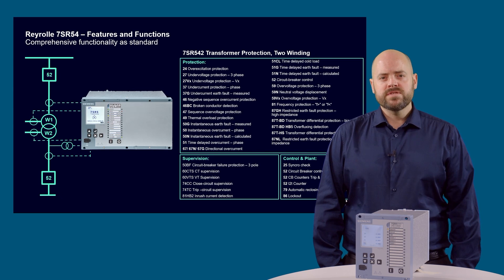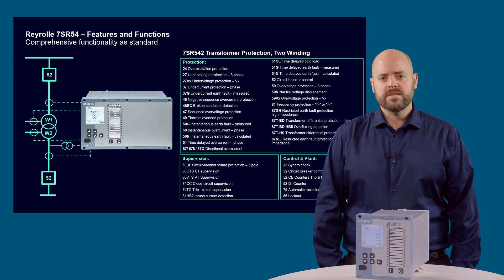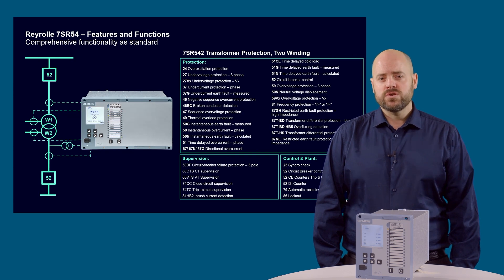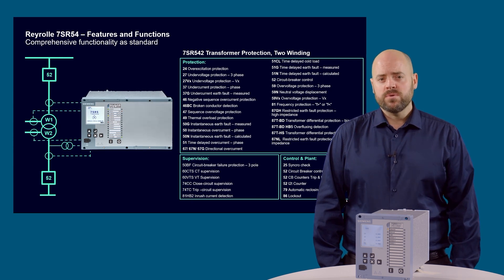The Reyrolle 7SR542 two-winding device provides comprehensive protection for two-winding transformers. The device also provides differential protection for reactors and motors. Its eight CT inputs are suitable for connection to both 1A and 5A current transformer secondary windings and includes a core range of functions as standard. Additional four VT inputs are also optionally available.